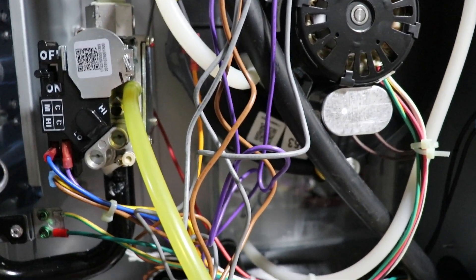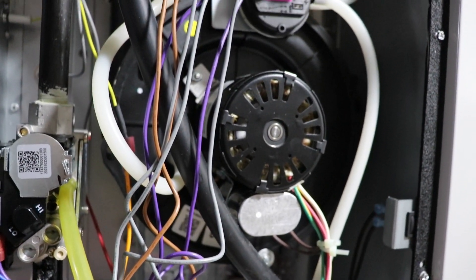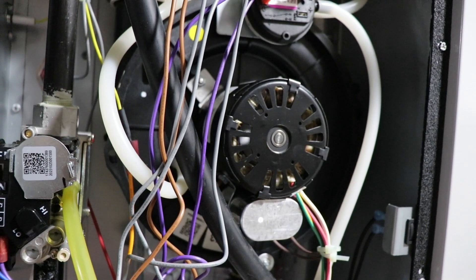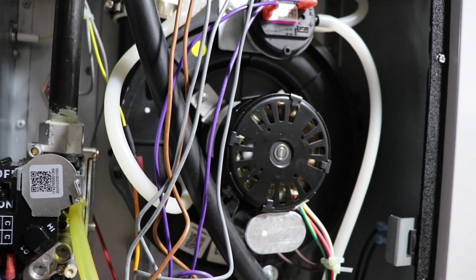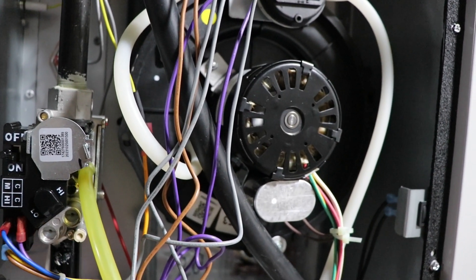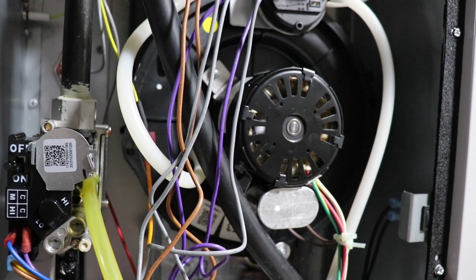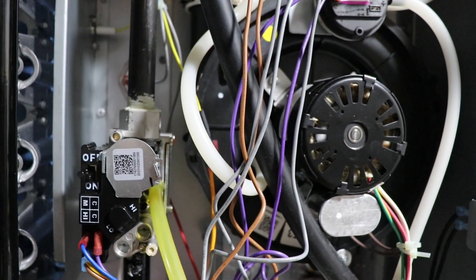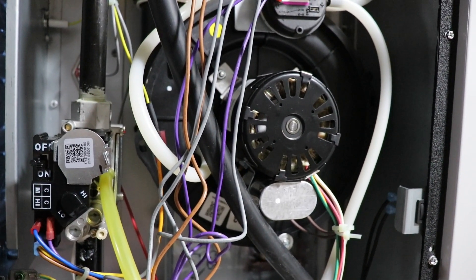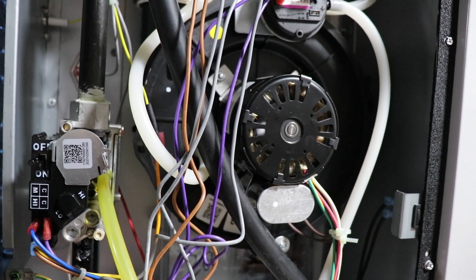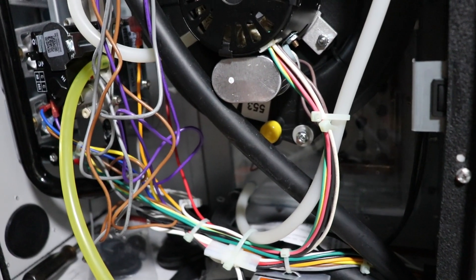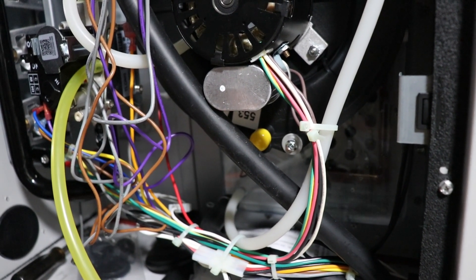We're firing away. I did have a problem where I could hear the fan, the inducer fan loading up with condensate, and it shut down. I'm not sure what that was about. It may just be it's just trying to clear itself out after the problems it's had running the last day. I don't hear any water or anything tingling around in it this time.